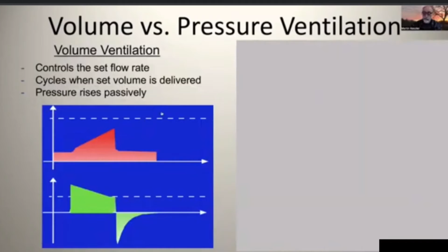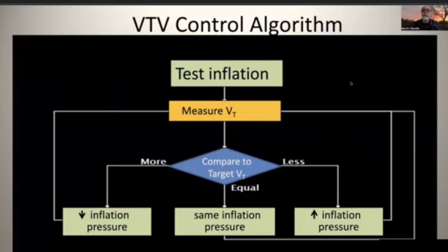The basic way that the algorithm works is there's an initial tidal volume generated with whatever pressure is initially used. The tidal volume that results is measured, apologies, and compared to the target tidal volume. And depending on whether the tidal volume that is measured is less than, equal to, or greater than target, the inflation pressure will be adjusted up or down or remain the same for the next cycle. So it's always looking back at the previous cycle, which is fine. It may take several cycles if there's a large change in compliance or change in patient's respiratory effort. And we'll talk about that a bit more later.